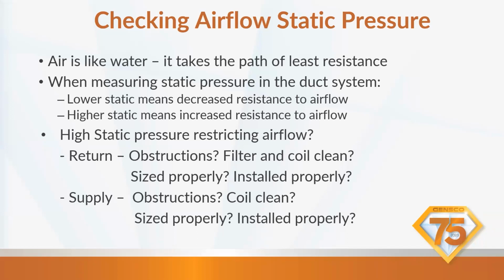If you have a high static filter, you're going to have to oversize that filter to get the pressure drop across it. So you might have to go to a 20 by 25 high static filter on a 3-ton gas furnace or heat pump, because you have to get that airflow. So keep that in mind. A 16 by 20 is way too small for a 3-ton, and I still see it a lot. But once I see that, we can start attacking the airflow and static pressure.